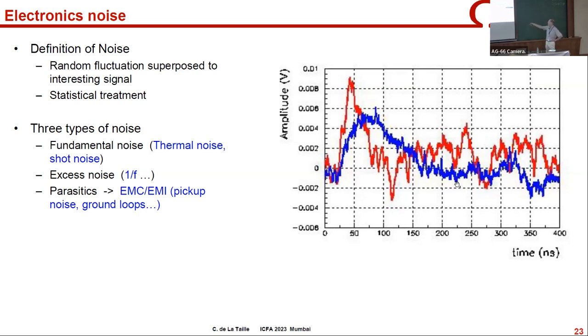It's the same preamp. And I don't know if you can see that on the red one, if you measure the amplitude, the real amplitude is 5 millivolts here. If you measure here, you are wrong by almost a factor of 2 because of the noise. So you see that this fluctuation on the preamp voltage output is due to electronics noise, and it immediately affects your measurement. I don't know if you see what's different between the red one and the blue one. It's the same electronics. There is only one thing which has changed.